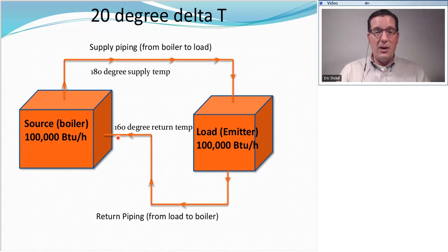As we're on the way up to 180, we have to pass 160 and 170, and then our return water temperatures are still 20 degrees lower than that. So while our supply water is 170, our return water is only 150, and so on and so forth. So the 20 degree difference gives us a good heat transfer and basically avoids some of the problems with low return water temperature. Now, in order for that to work, we also have to have a 20 degree delta across the emitters. So we are adding heat here, and we need to be rejecting heat at the same rate across the emitters. And this is all related to water flow rate.